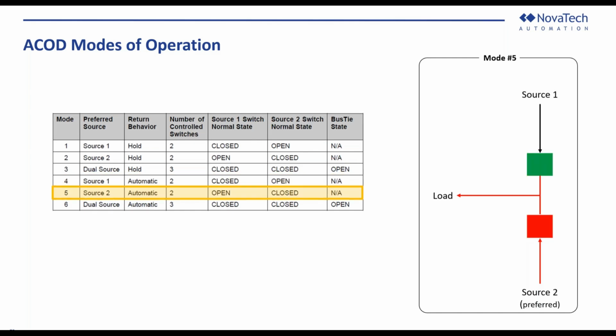And then for mode 5, it follows the same pattern, with source 2 being the preferred. It will go through the same steps if potential is lost, transferring over to source 1. And while it's operating on the alternate, source 1, it is monitoring to see if potential returns. And if it does, and it meets the criteria, it will switch back to source 2 as the preferred.